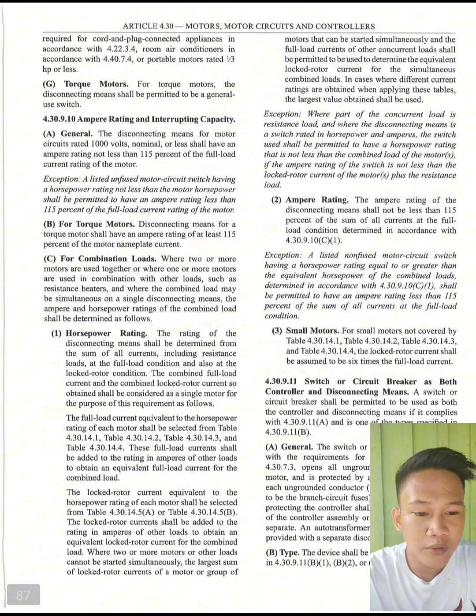Third, small motors. For small motors not covered by Table 4.30.14.1, Table 4.30.14.2, Table 4.30.14.3, and Table 4.30.14.4, the lock rotor current shall be assumed to be 6 times the full load current.